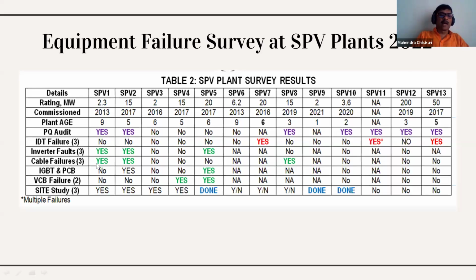Now if you look at other failures: cable failure again 3, IGBT PCB failure 1, VCB failure 2, and inverter faults 3. For PQ audit, only half of them said it was done. Looking at plant age, some are old and some are new, though actually many of them are old, only a couple are new.